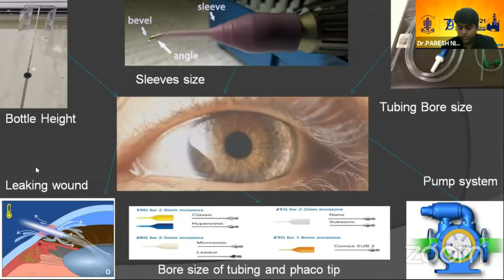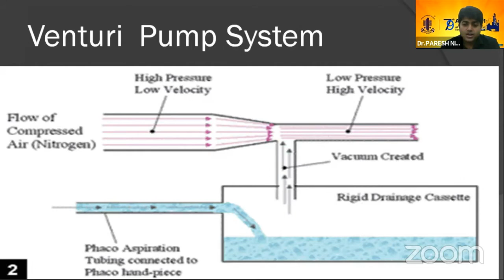So if we talk about different pumps, there are majorly two pumps. The first is the peristaltic, the most commonly used. The peristaltic pump basically uses a roller which compresses the phaco tubing, creating a continuous milking action, which is responsible for the aspiration of the fluid from the eye and generation of the vacuum once the tip is occluded. Whereas in the Venturi pump system, there's a high pressure, low flow air which is transmitted to make low pressure, high velocity, creating a vacuum which is transmitted to the eye via a rigid drainage cassette.